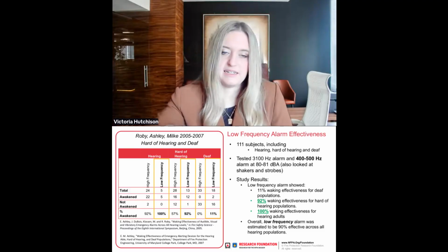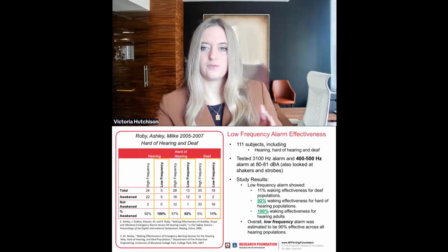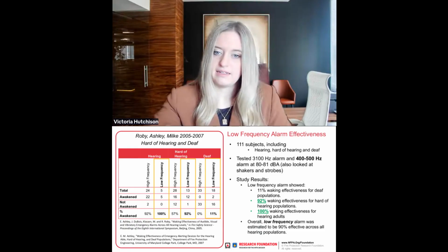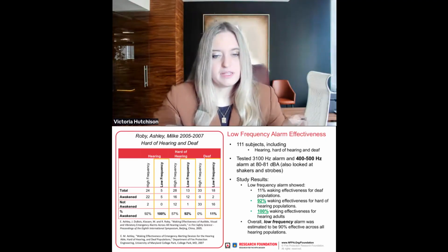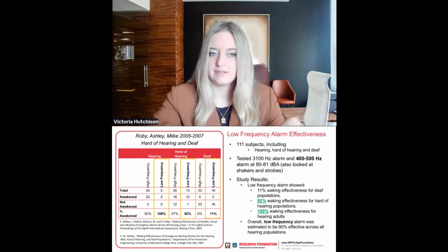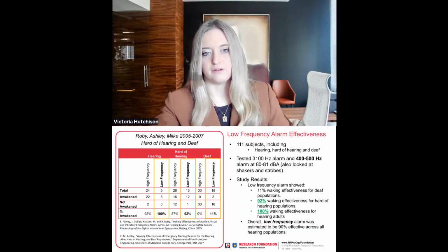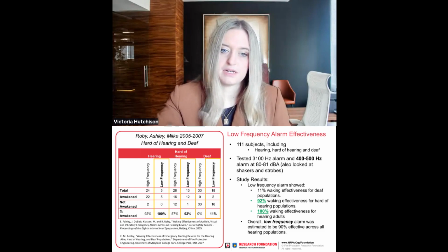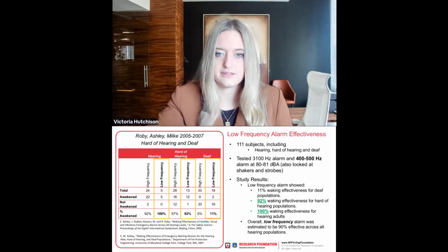Going back to the study we looked at a moment ago, but from the low frequency side, looking at the 400 to 500 hertz alarm put out at 80 dBA. In terms of the deaf population, it's still low: only 2 people awakened, but there was some movement there for the deaf community, which is a positive sign, a jump up to 11% compared to 0%.